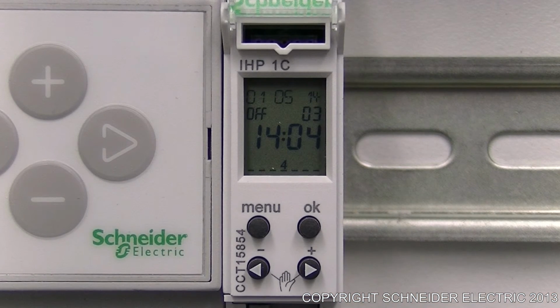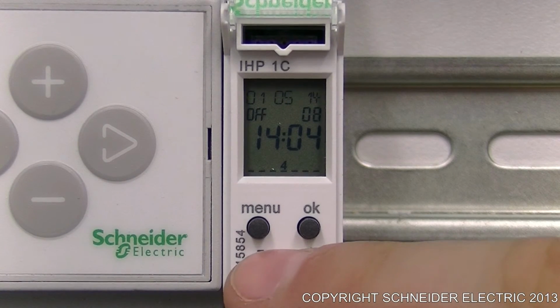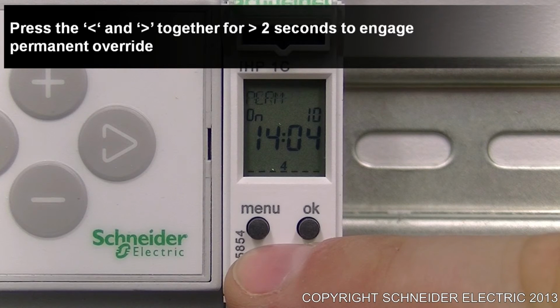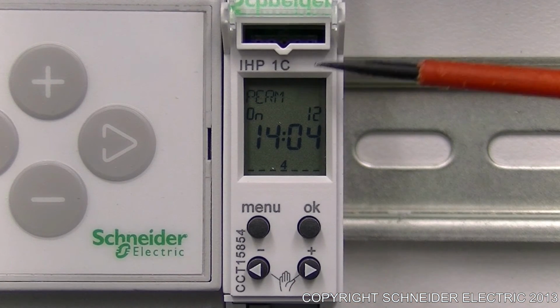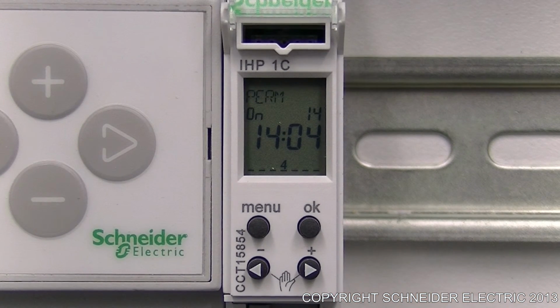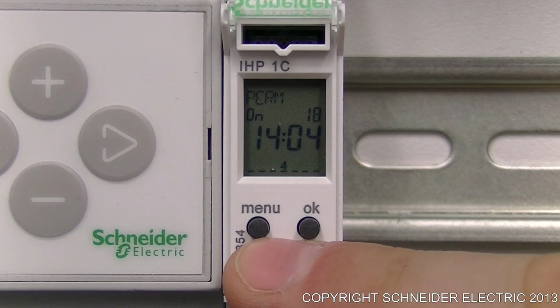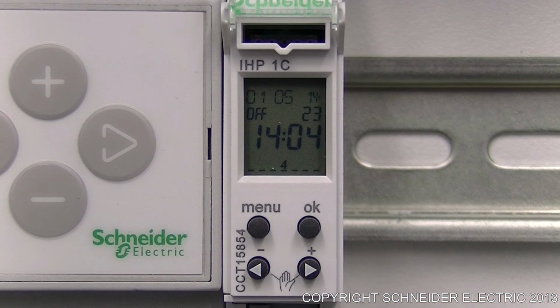To have those loads turned on permanently, if you press and hold these two buttons, you'll see that the override turns to a permanent. So up the top here, it went from override and now it's gone to permanent. So it's a permanent on now. To cancel it, press and hold those two buttons for a couple of seconds and it cancels it.